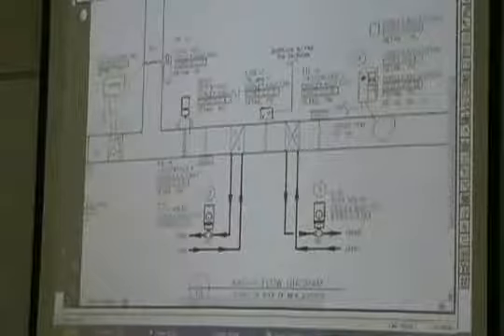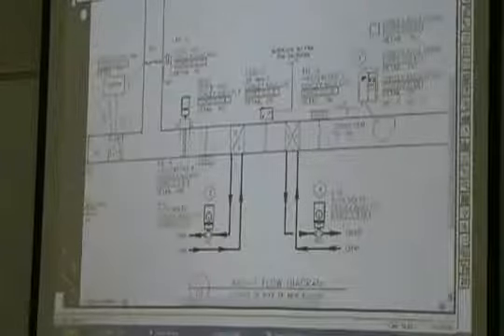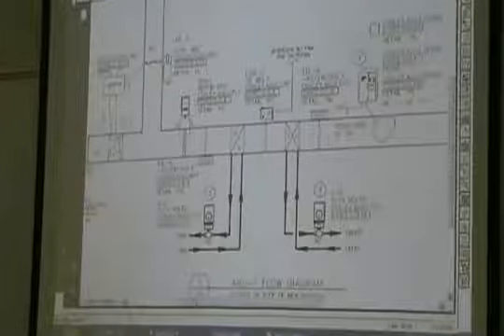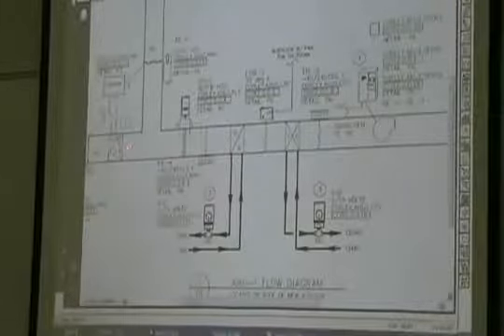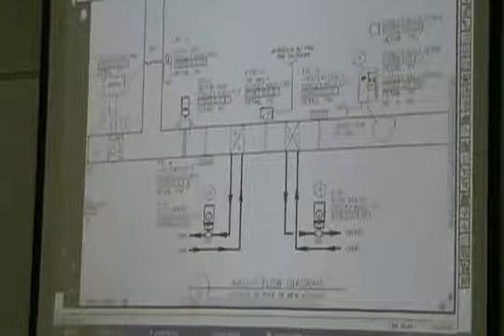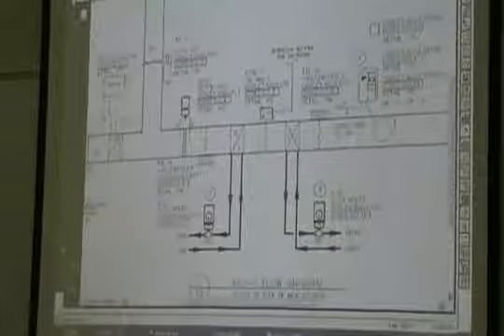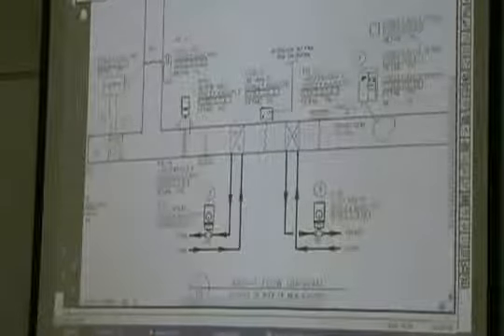Says that the heating shall be disabled when the outdoor airflow rate exceeds the required minimum airflow set point by more than 10%. Okay, all he's saying is that if we're above our minimum airflow, then we don't want to use heat. Okay, he's just trying to make sure that we back the damper down to that minimum before we actually use any heat out of the coil. That's all he's saying by that right there.